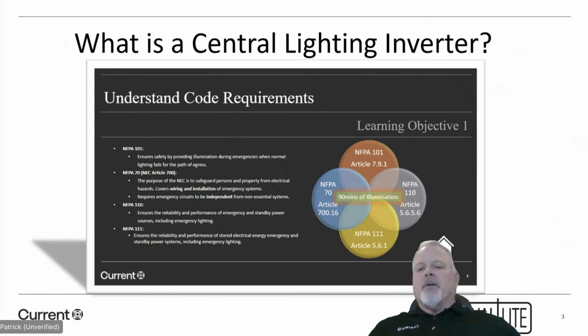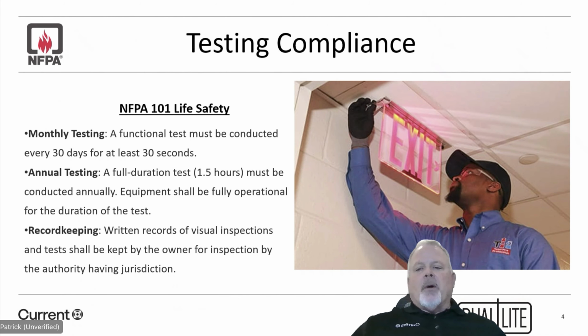One of the things that we have to take into consideration when we talk about our central lighting inverter is code. As you can see, there are several codes here that are related to UL 924 product. The one that we're going to focus mostly on today is the NFPA 101. Now, this particular code really goes around lighting our path of egress, as well as the testing requirements, both monthly and annually. Testing compliance. So under NFPA 101 life safety, there has to be monthly testing. A functional test must be conducted every 30 days for at least 30 seconds.